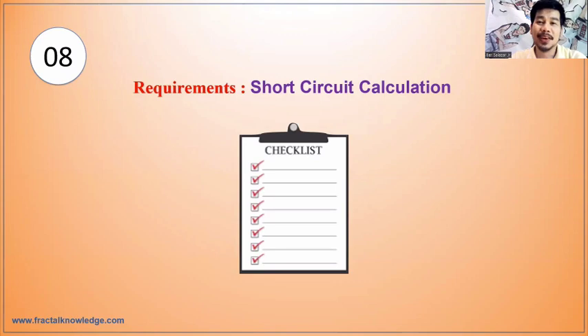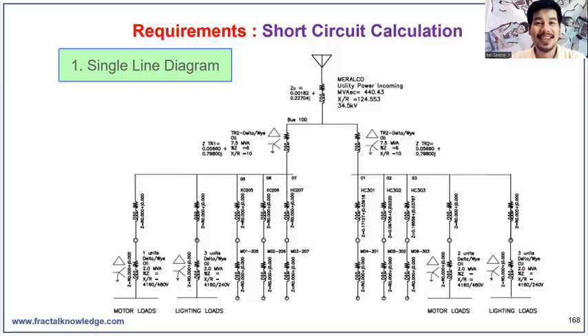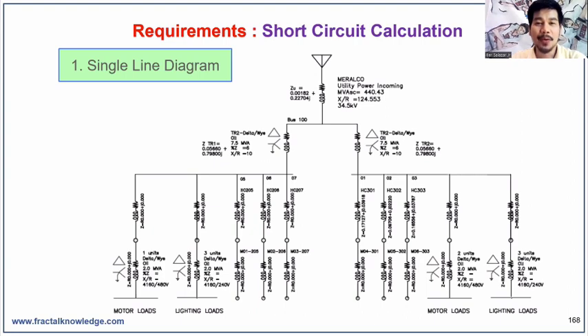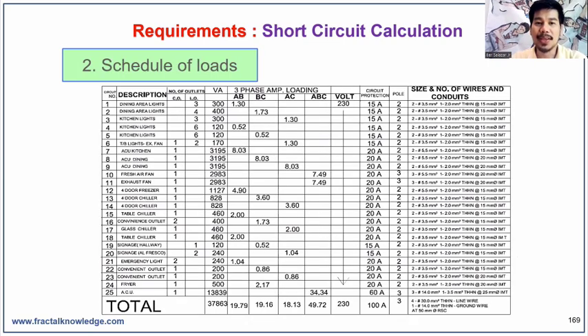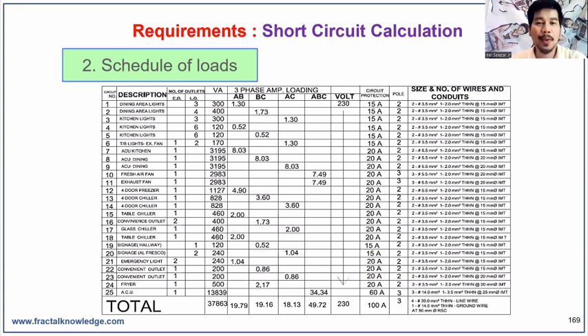Now let's proceed to the requirements of short circuit calculation. First, you need to have a single line diagram reflecting all the electrical components. When you are invited to do the electrical design analysis of a certain establishment, whether commercial or industrial, you need to see the single line diagram because that is the number one requirement to start electrical design analysis. The second requirement is to get the schedule of loads, which includes the kVA load, load current, the size of wires, and when available, the length of wire.